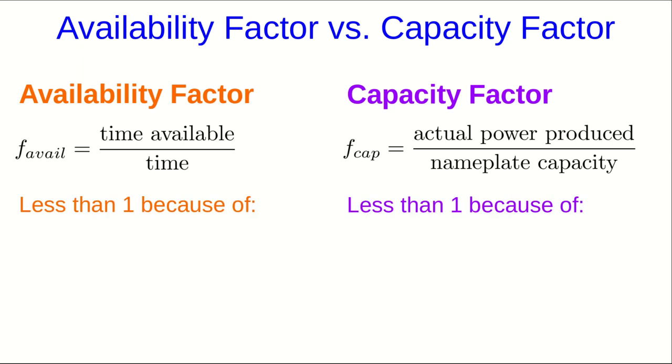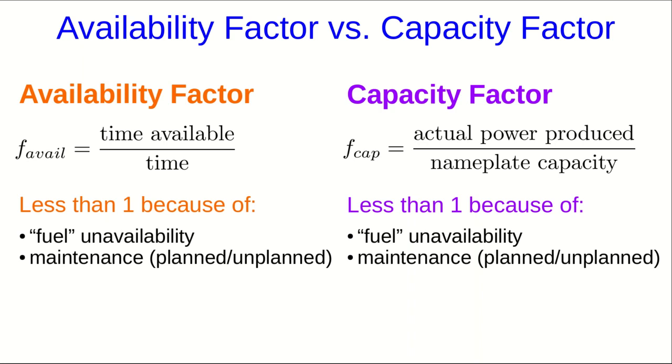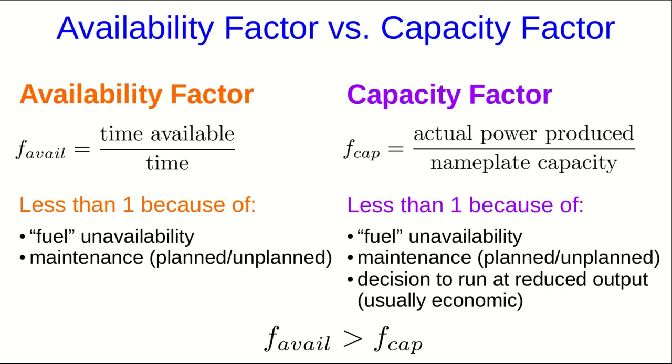Both of these tend to be less than one because of different causes. Availability factor can be less than one because of fuel unavailability, where things like wind and sunlight count as fuel, and or for maintenance. Capacity factor can be less than one for all of those reasons, but also because of decisions, usually economic decisions, to run at reduced output. So the availability factor is always greater than the capacity factor.